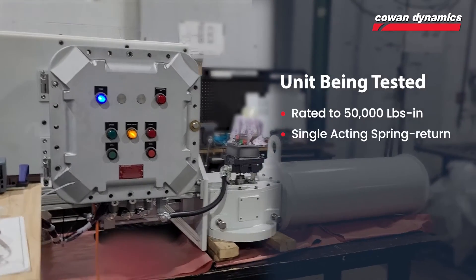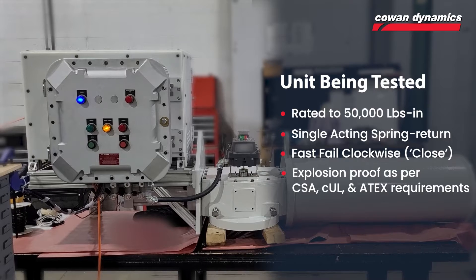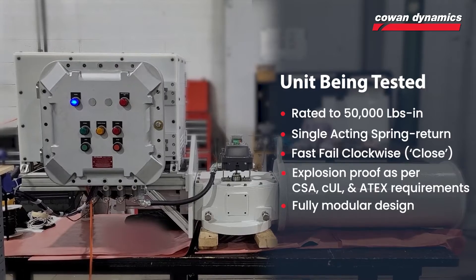The unit being tested is rated to 50,000 pounds-inch, single-acting spring return fail clockwise. The complete assembly is explosion-proof as per CSA, CUL, and ATEX requirements, and it features a fully modular design.